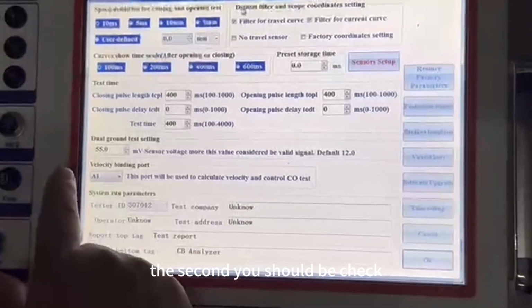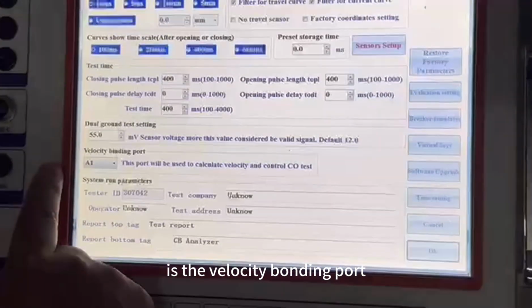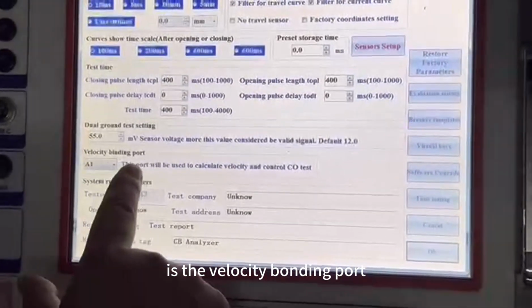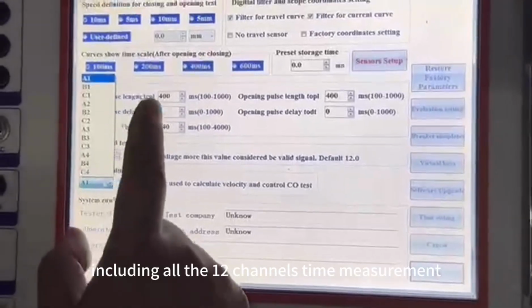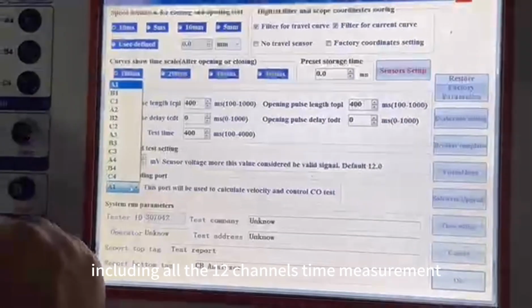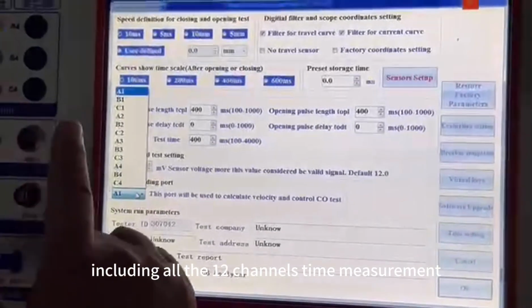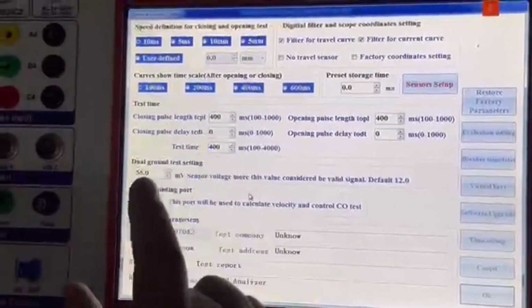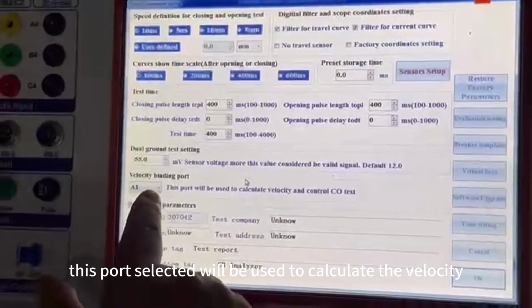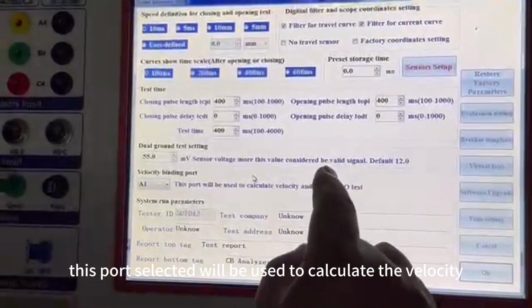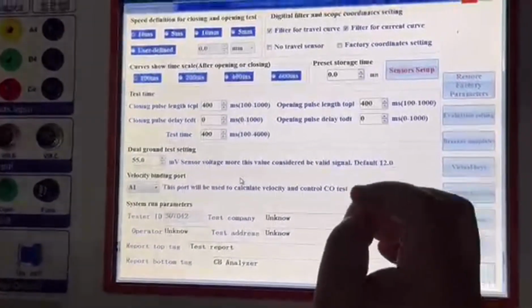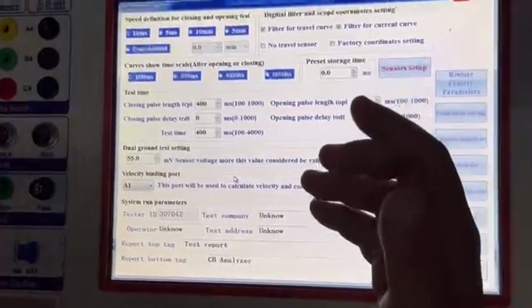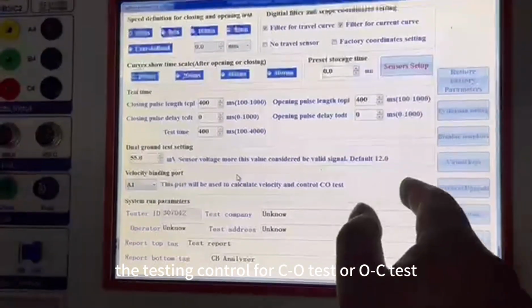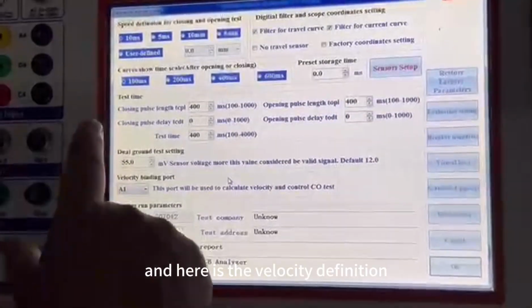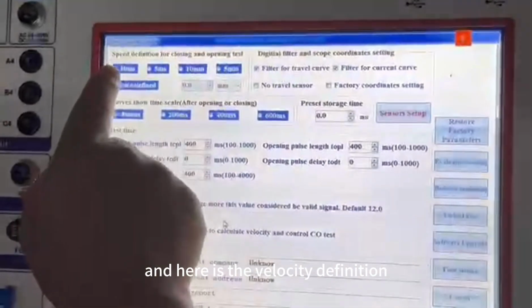The second thing you should check is the velocity binding port. Here the selection could include all the 12 channel time measurement ports. The port selected will be used to calculate the velocity and the testing control for the CO test or OC test. And here is the velocity definition.